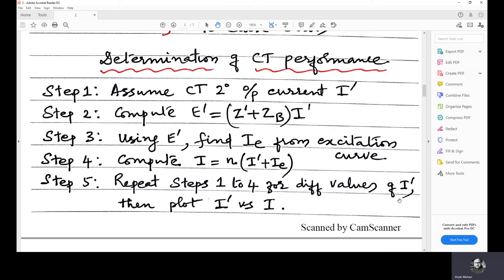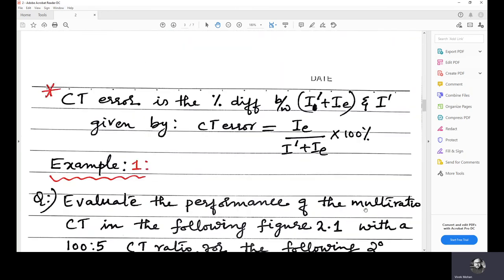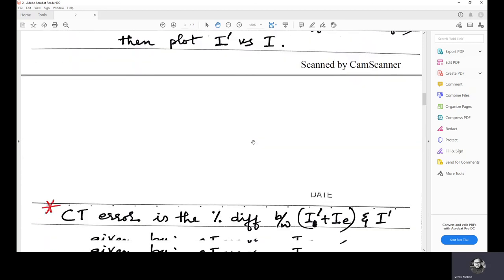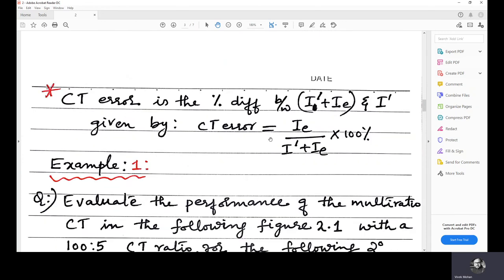There is a corresponding threshold at the level of i' at which the relay should operate, so this difference should be small. Because of a high value of ie, the CT should not reproduce an inaccurate current seen by the relay. To quantify this, we find the CT error in percentage, which equals ie divided by (i' + ie). If ie is high, the CT error will be more, because i' may not reflect the actual fault current in the power system. We will now go through some examples to illustrate this.